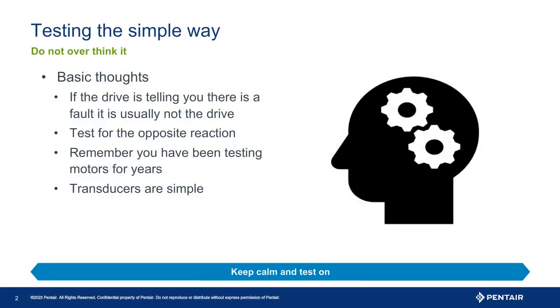The key today is not to overthink the issues. Motor and transducer issues are common, but not hard to diagnose. Remember these few tips. If the drive is telling you something, it is often not the drive. What is the opposite reaction of the fault showing? Remember, first and foremost, we are pump people. Motor testing is still the same testing we have been doing all these years. Transducers, on the other hand, either work or do not, and simple testing often works well.